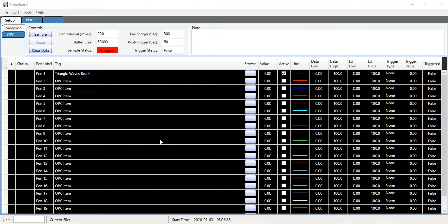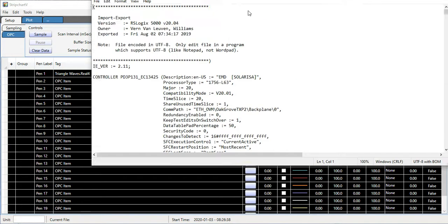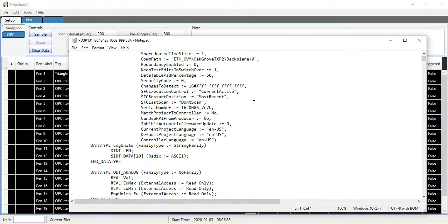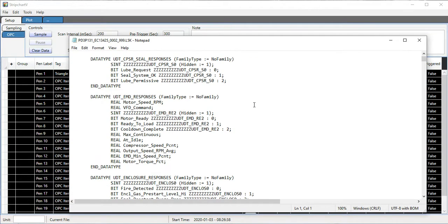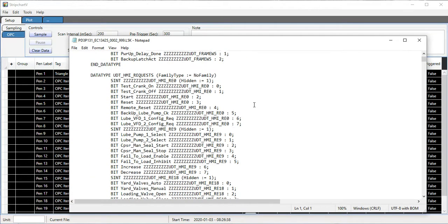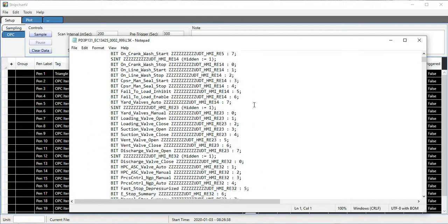An L5K export file is created through Studio 5000 or RSLogix, where you would do a file and save as, and then choose the L5K file type. That's just a text file. I'll show you what it looks like if you open up an L5K file. It's the complete contents of the processor as a text file.